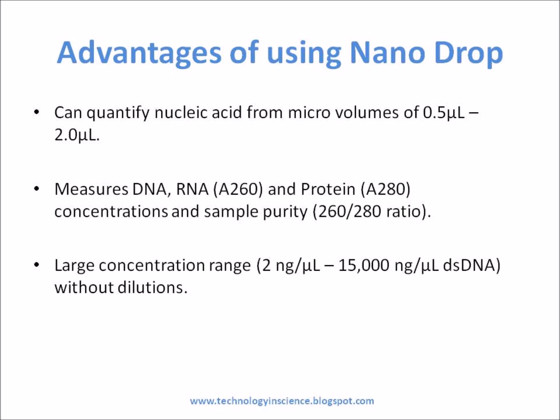Nanodrop is a UV-visible spectrophotometer device from Thermo Scientific, which can quantify nucleic acid from micro volumes of 0.5 to 2 microliters. Features include direct, easy measurements in less than 5 seconds — just pipette and wipe. It measures DNA, RNA, and protein concentrations and sample purity, with a large concentration range of 2 ng/µL to 15,000 ng/µL for double-stranded DNA without dilutions.